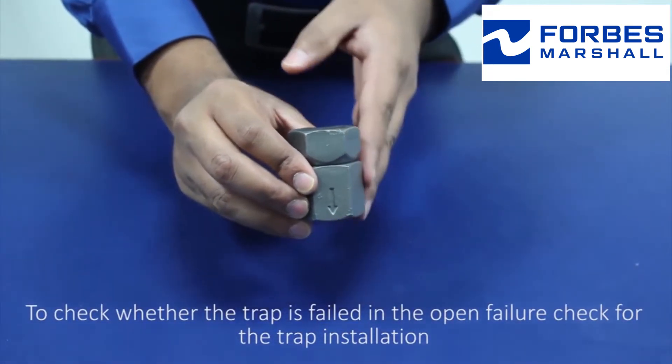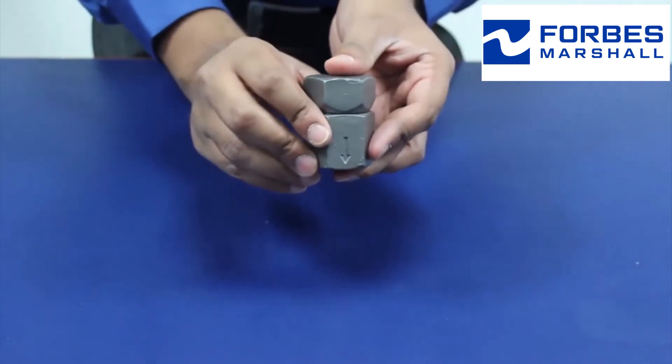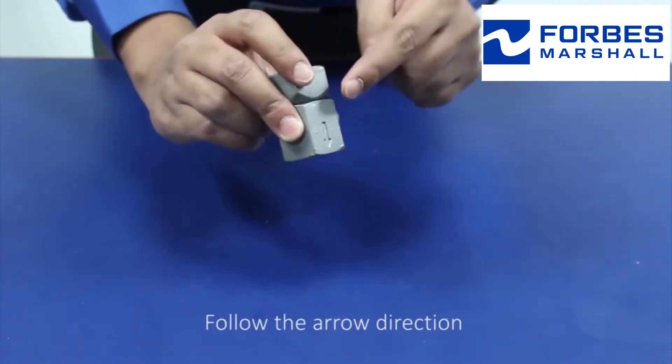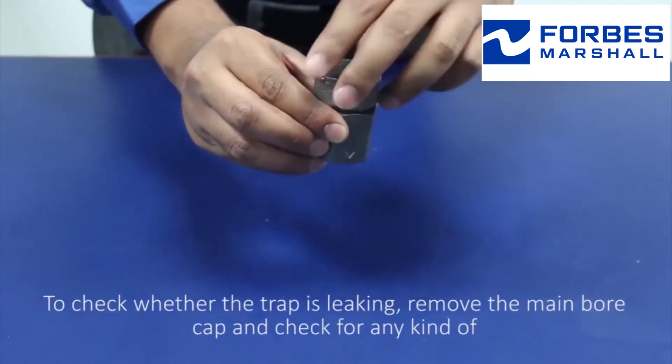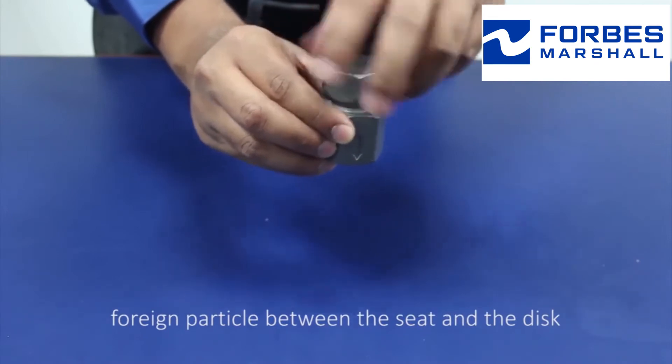check the trap installation — horizontal inlet and vertical outlet. The inlet port and the discharge port follow the arrow direction.